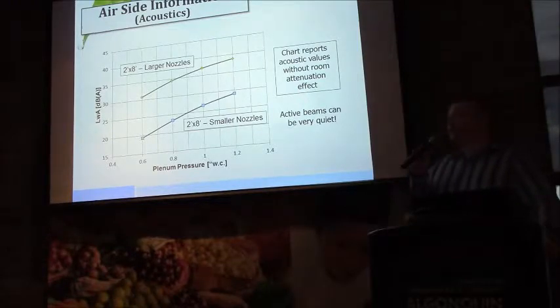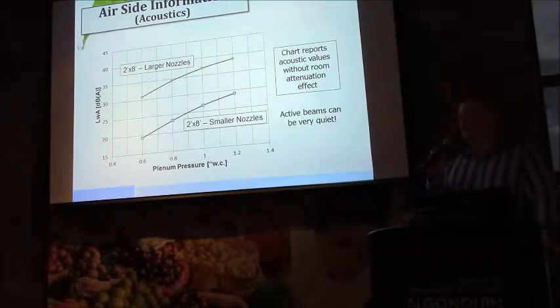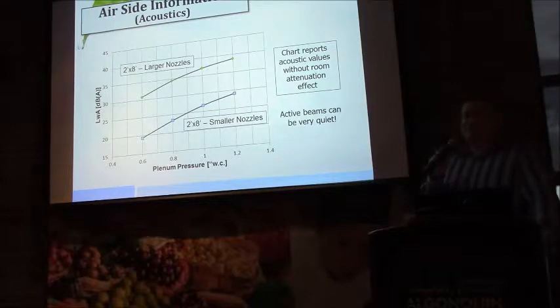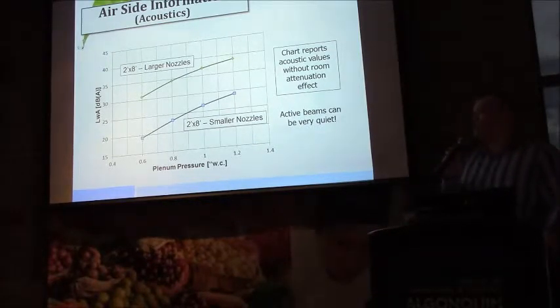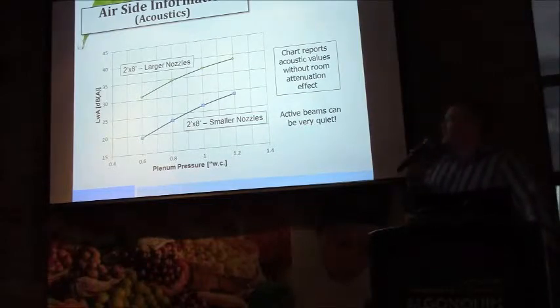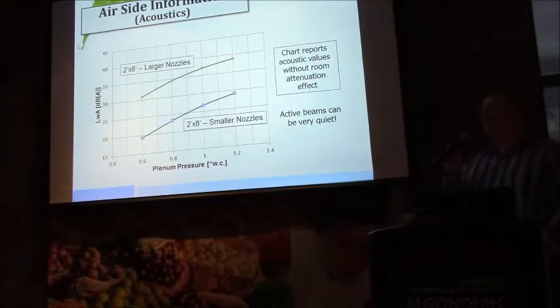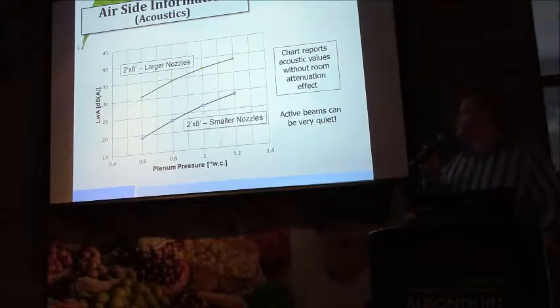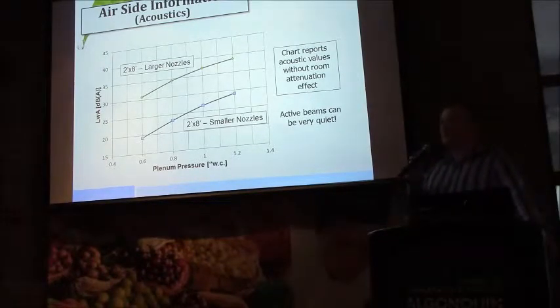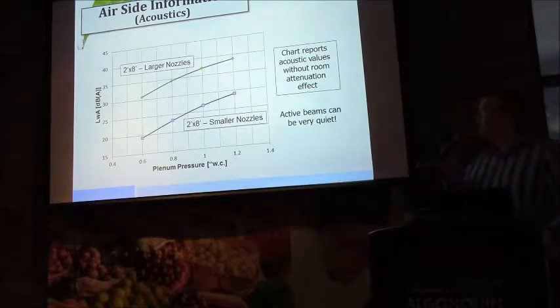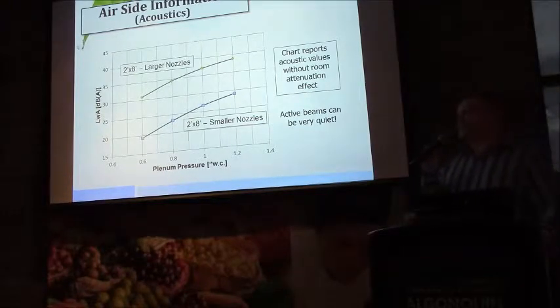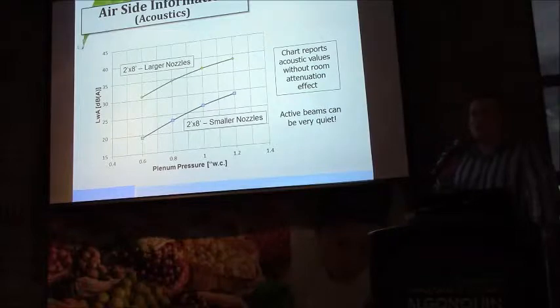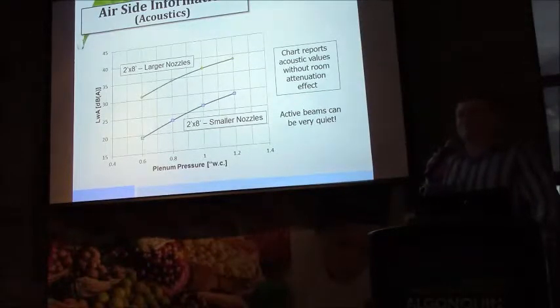The acoustic signature or the sound in the space is generally not driven by the beam itself. It may be flow-generated noise because of large pressure drops or other equipment in the space. Oftentimes, it's very easy to design an active beam job to an NC criteria that is, by most standards, considered to be quite aggressive. But the general rule follows that larger nozzles make more noise, and higher pressure also generates more noise.